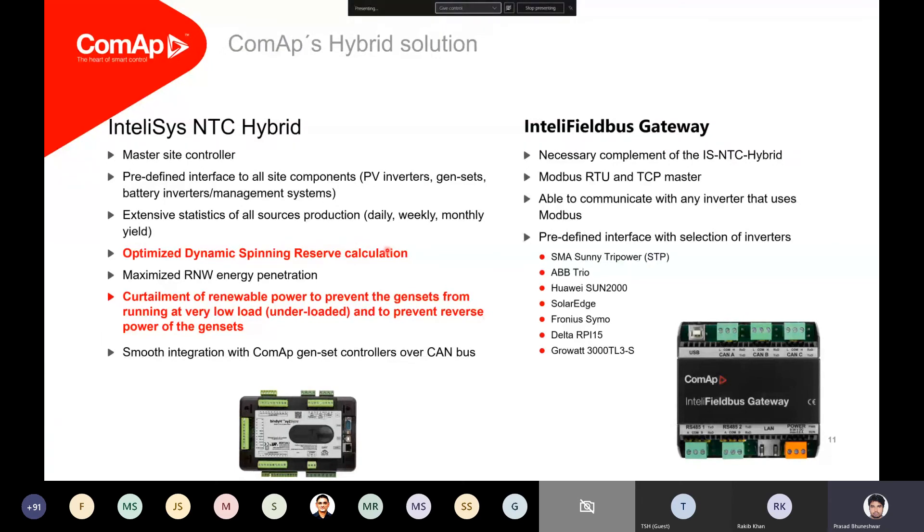On the right-hand side we have a module called the InteliFieldbus Gateway, which is essentially a communication bridge. It allows us to talk to different inverters, BMS systems, battery management systems, or any other Modbus or TCP-based systems — RTU or TCP. We can communicate with almost all possible inverters available in the market, curtail them, control them, and make them work in a more efficient manner with respect to the site requirements.